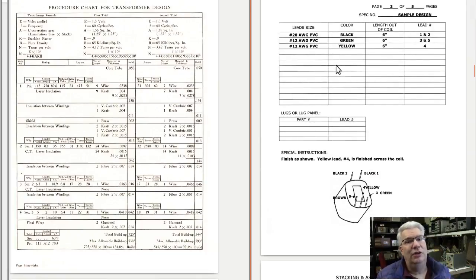All right, so I've taken all his design procedures, and I've made 3 Python classes for this. There's 2: the winding class and the transformer class. What you end up doing is typing in a little bit of Python code, which we'll show here in a minute, and then you build your transformer with the windings in the order that you want to wind them. And then you get a chance to modify all these parameters that he's iterating on, and you get to do a real design by manipulating all the parameters.